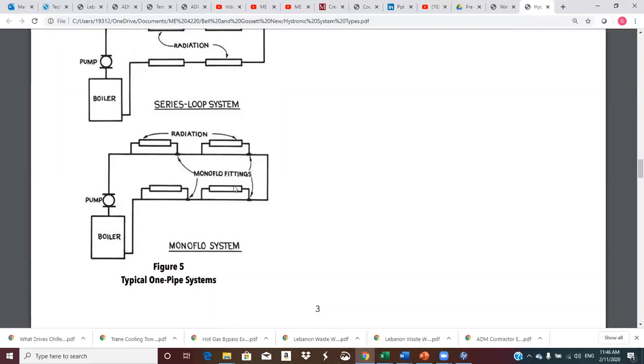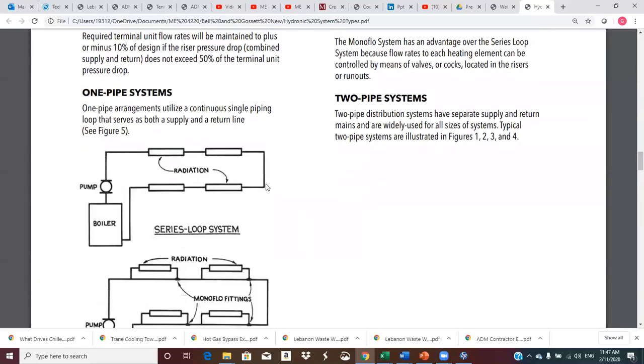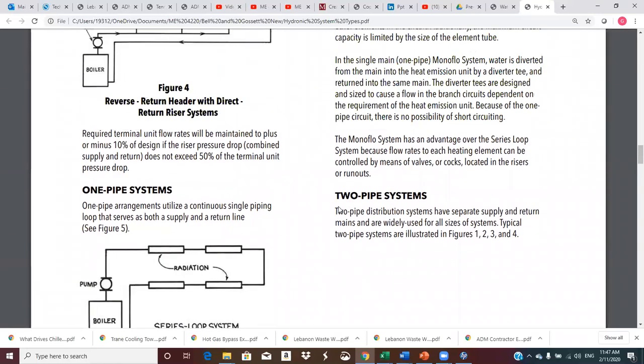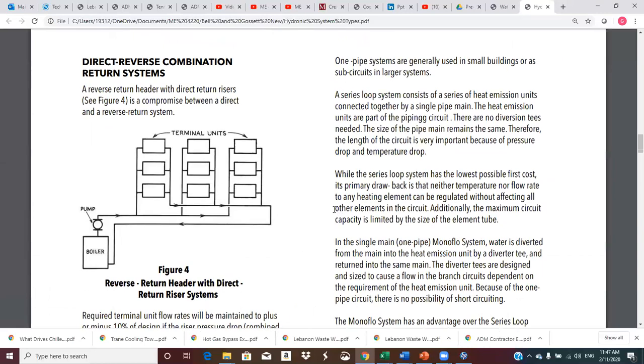You can do it like this. This is a trade name, these Monoflo fittings. They will adjust the amount of flow here. It will take out a certain amount here, put it in and mix it, take out a certain amount here, etc. So that's a way to adjust the amount of flow that goes through each coil instead of putting all of the flow through the coil. You know, one pipe systems, small buildings, sub-circuits, generally speaking, you don't see a lot of that.